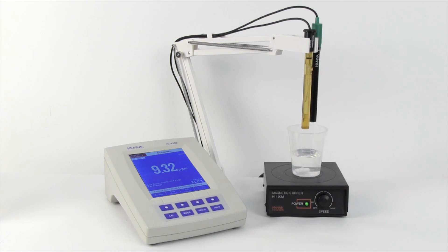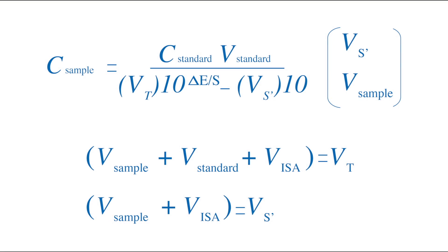The HI4222 has the calculations for the known addition method pre-programmed into the meter. For this calculation, shown here, we will need the following values: the volume of the sample, the volume of the standard, the concentration of the standard, the volume of ISA, and the voltage change before and after the addition.